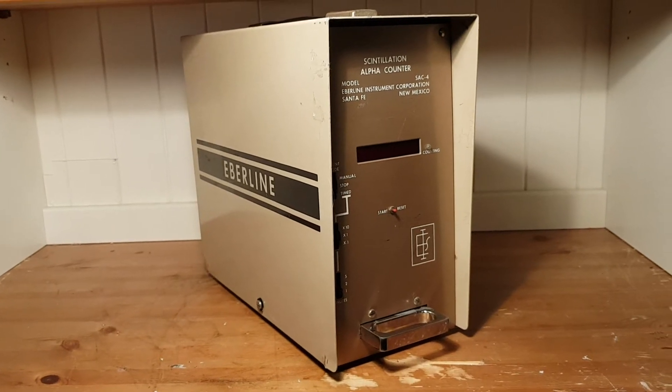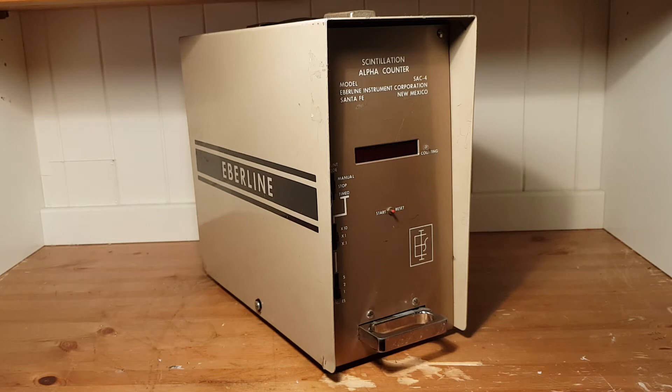Today I have something fairly special and unique to review. This is an old alpha scintillation counter from the 70s — a model SAC-4 made by Eberline Instrument Corporation. It was mainly used to monitor alpha activities in air filters in different facilities, but I suspect it was also used to monitor general contamination, such as wipe tests of different surfaces and sources. This is exactly what you'd want to use it for as a private individual. For example, checking contamination on a surface, checking if an old americium source or a radium clock is leaking. It is very useful for such purposes and I would highly recommend getting one if you ever find one for cheap.